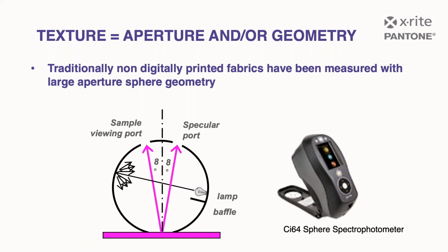And a sphere instrument is different in the sense that it uses this big globe of illumination to get very soft illumination on the piece being measured, and then can have a couple of different ways of capturing data from it, with the included specular reflection or not. But it gives a different look to the instrument when it's measuring.